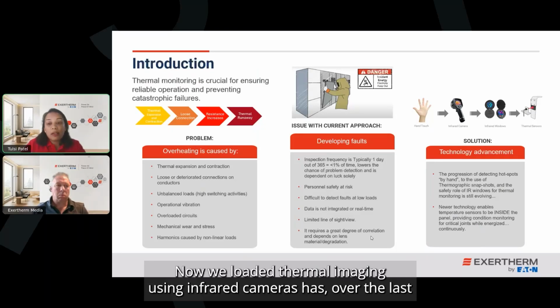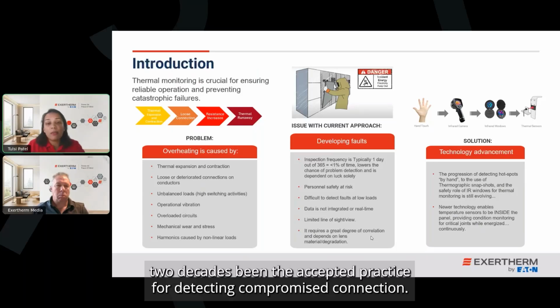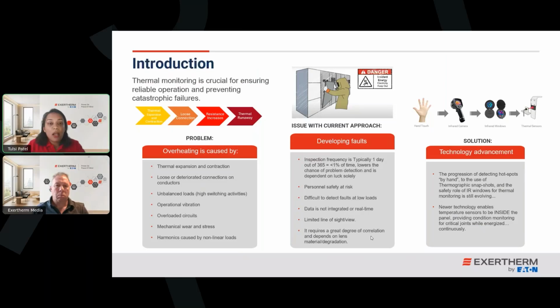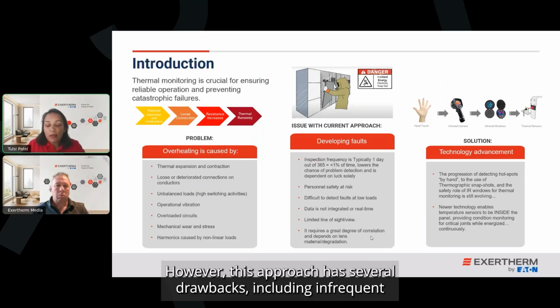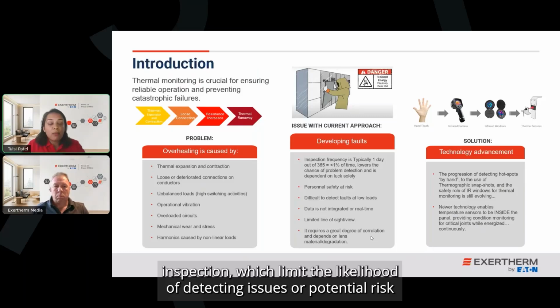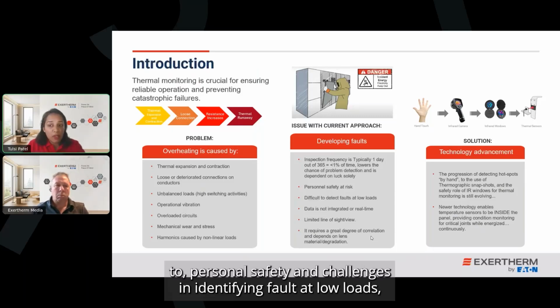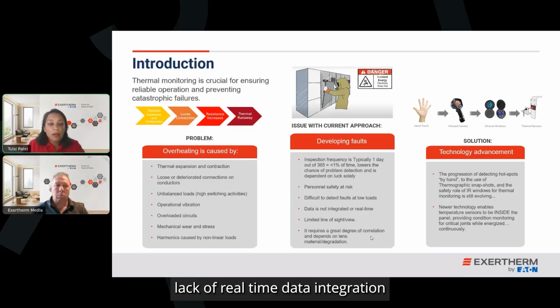Now, periodic thermal imaging using infrared cameras has over the last 2 decades been the accepted practice for detecting compromised connections. However, this approach has several drawbacks, including infrequent inspection, which limits the likelihood of detecting issues, potential risk to personal safety, and challenges in identifying faults at low loads, lack of real-time data integration, and constraints related to line of sight.